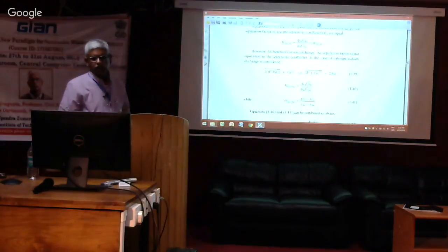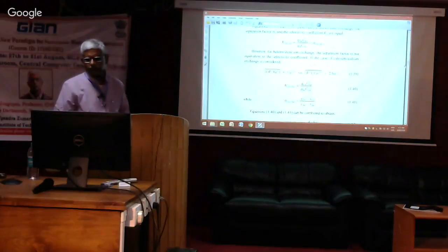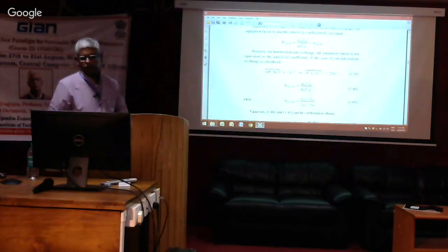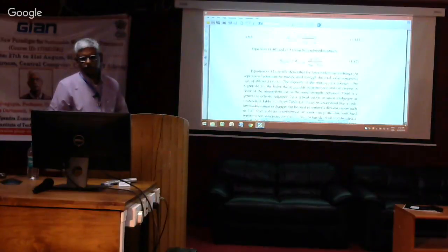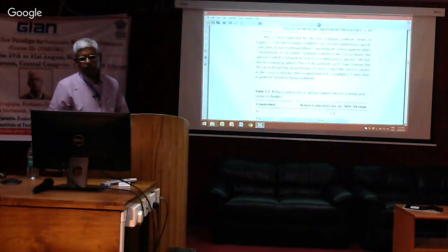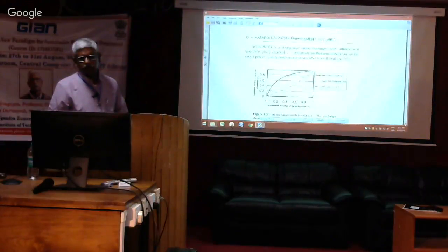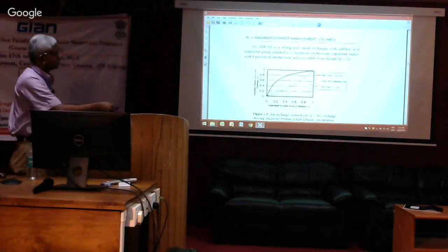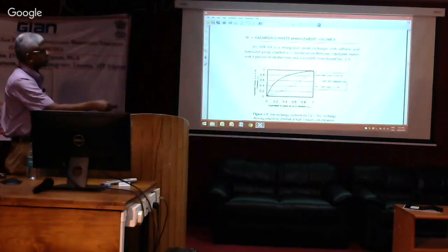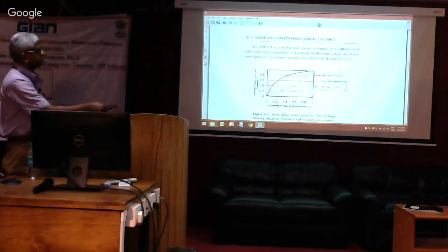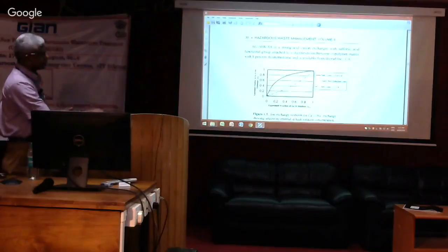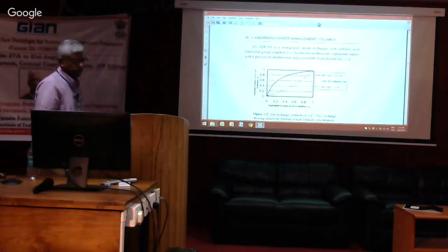sodium chloride. And by that, what are you doing? You are asking the reaction to go in the reverse direction. So when you go in the reverse direction, you are basically trying to create a situation like this where now sodium becomes more preferable. So, in the normal exhaustion run, calcium is preferred. When you are regenerating, sodium is preferred. That's what we do. Okay?